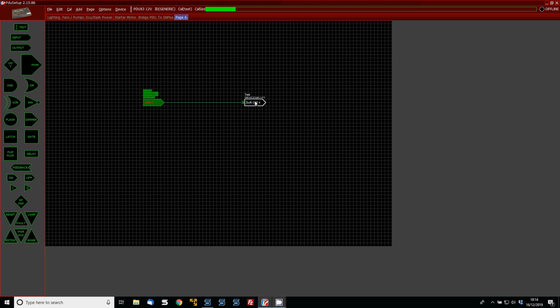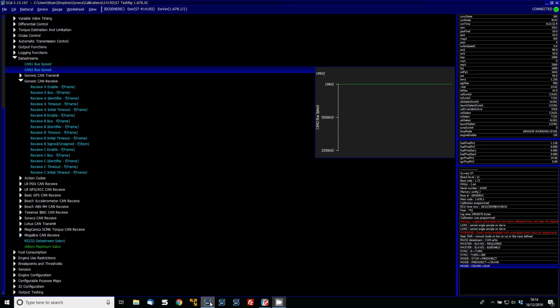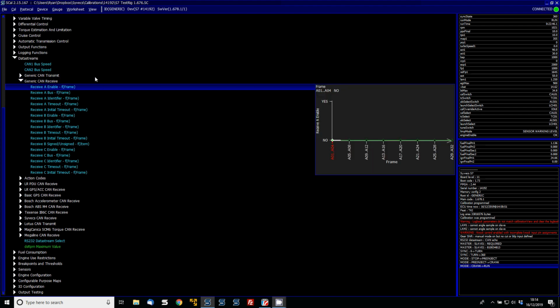So what we need to do now is go to the ECU side and set up the generic CAN receive to receive that message being sent from the PDU. Because the items that come from the PDU just take up 8 bits, there's no point using the receive A items, because they're for 16-bit bytes of data.